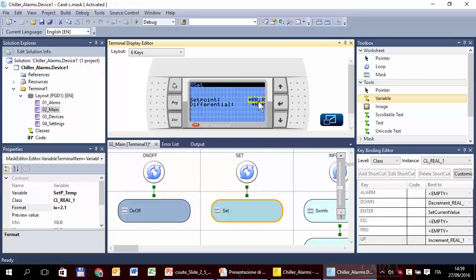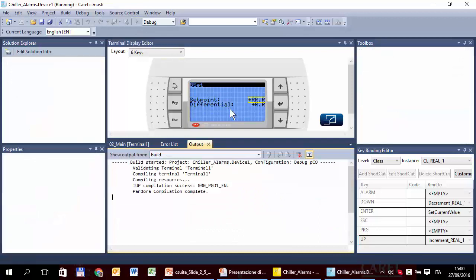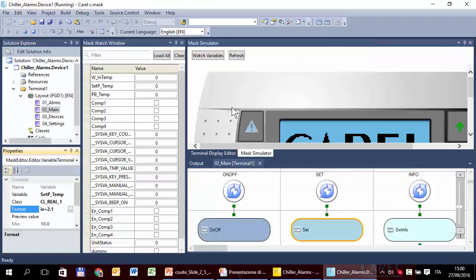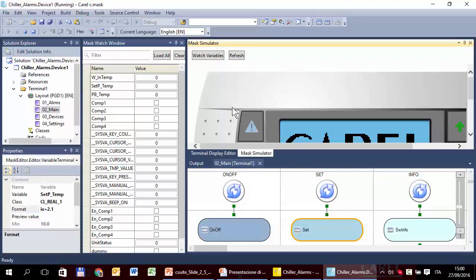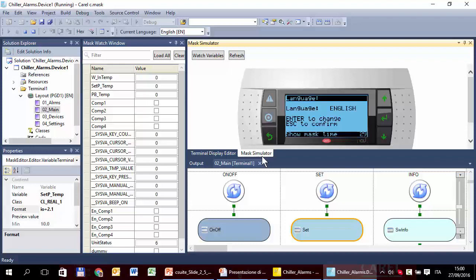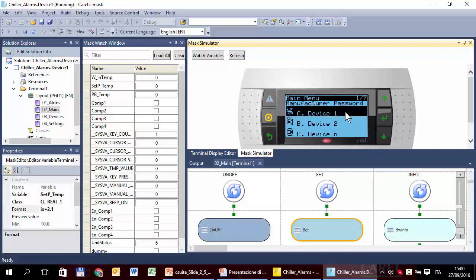What's next? The configuration parameter, the enable of compressor 1, 2, 3, 4. In this case, we can use one of the existing menu. There are some generic menu. We can use one of these for our target. That is, where to place the four variables to enable the four compressors. We can use the last one. Why? Because we already have the icon of the compressor here. While if we used the first one, we would need to change also the icon. So, I will use the third menu, the one for device N.